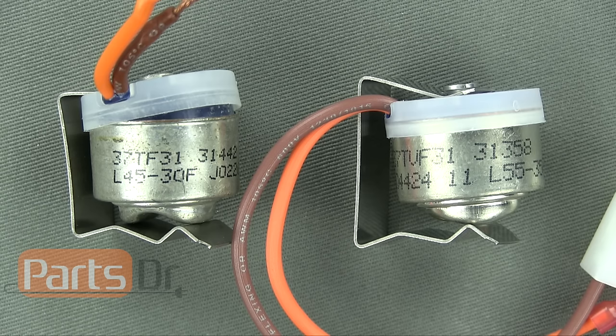If your defrost thermostat visually is raised up like this, then you should replace the thermostat even if it passes the continuity test.